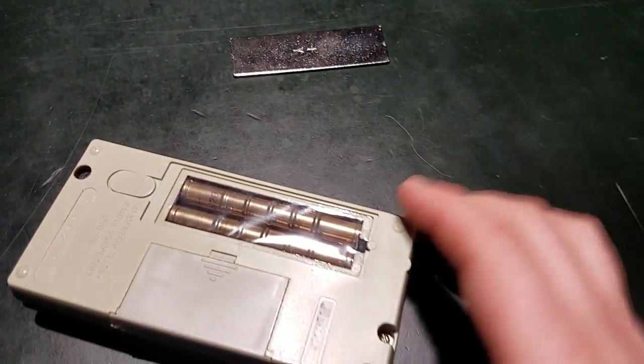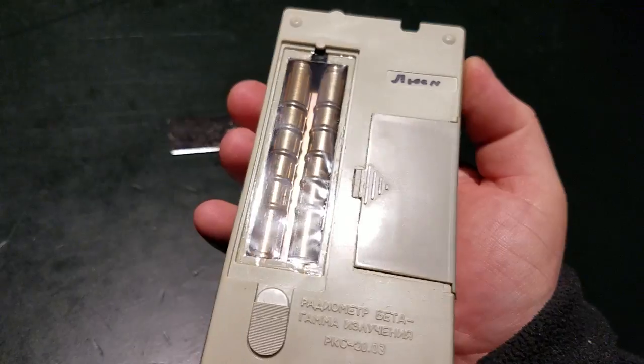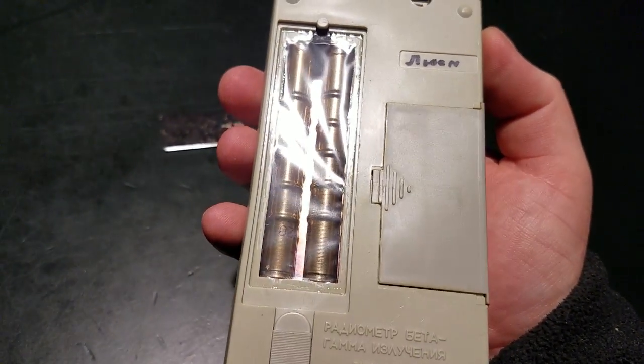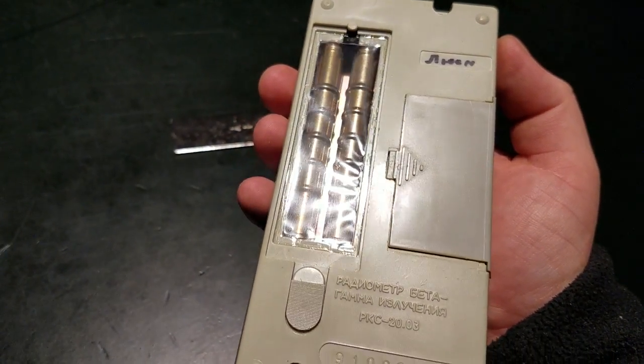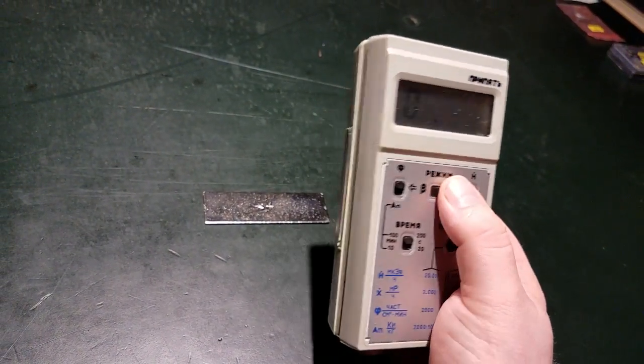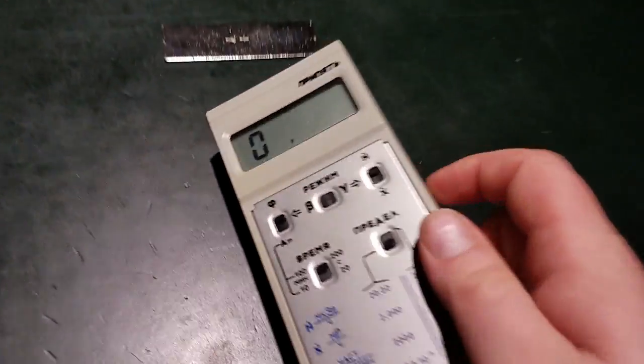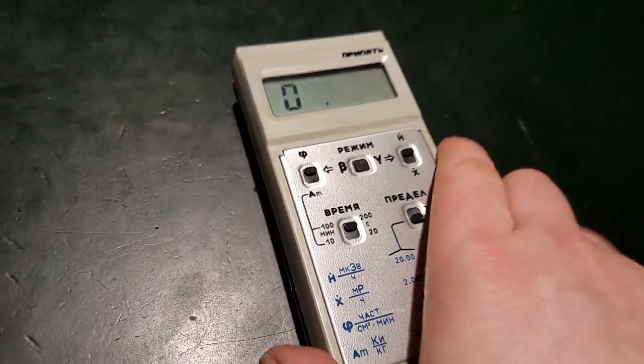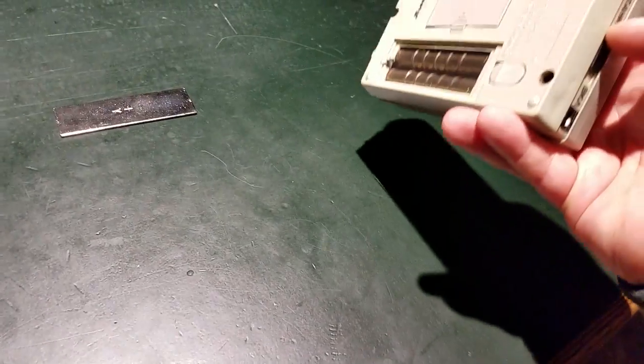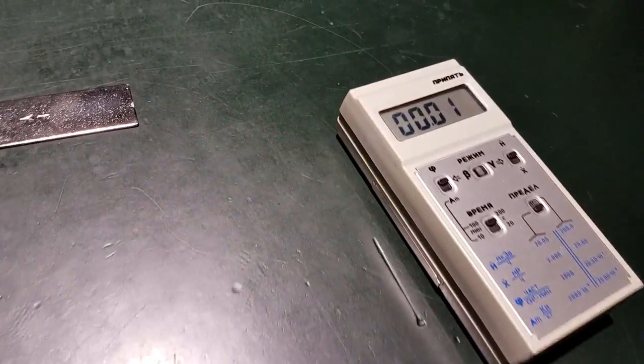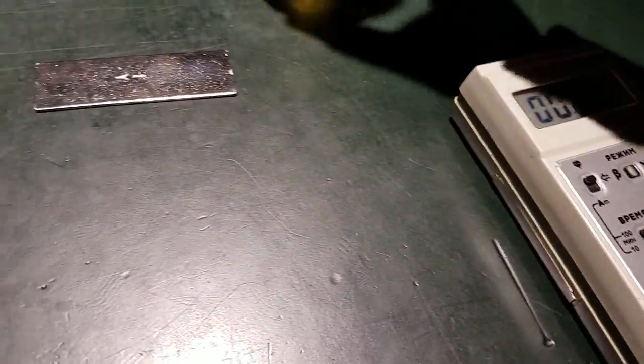Okay, beta shield is off. You can actually see there's a thin plastic layer protecting the tubes from contamination or getting touched. We'll pop it over to beta mode and we will do beta flux density. Now I'll power this guy on and we'll test against this.